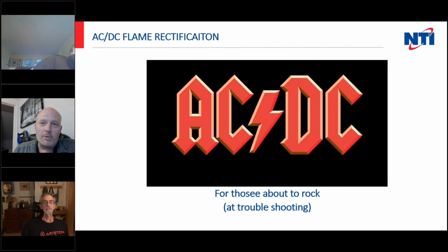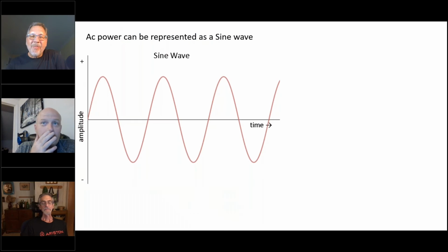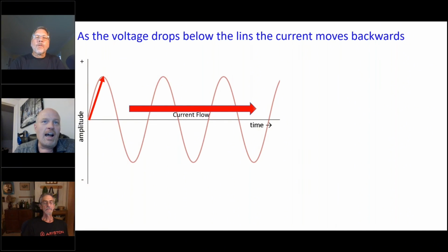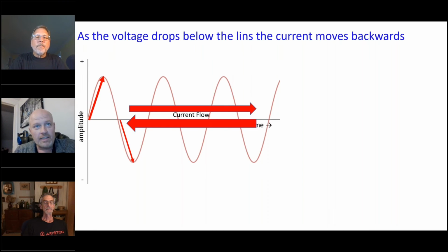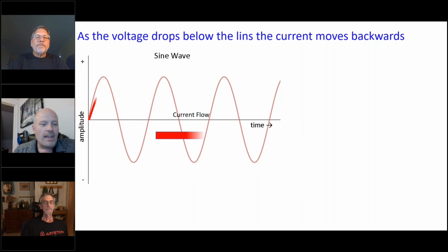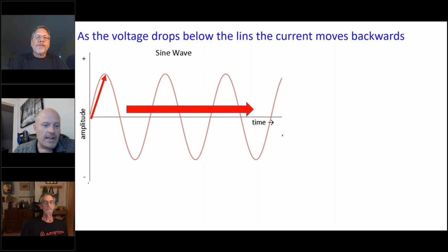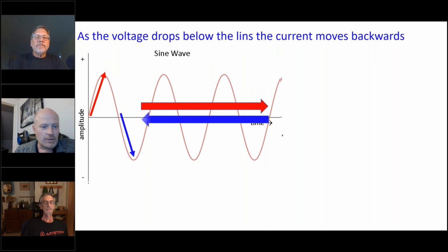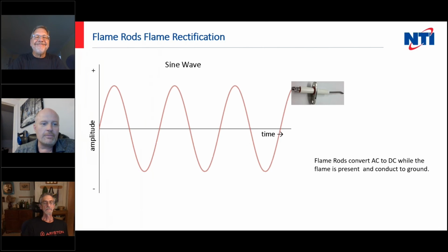Okay, now we get on to AC/DC flame rectification and my favorite band. So for those about to rock at troubleshooting, we're going to go over some flame signal. We call it flame rectification because the flame rod takes this AC signal. Our current goes to the right as the voltage increases. As the voltage decreases, the current goes to the left, and back and forth. This will happen over and over again. I don't remember how long this slide goes on for. There we go, not too long.